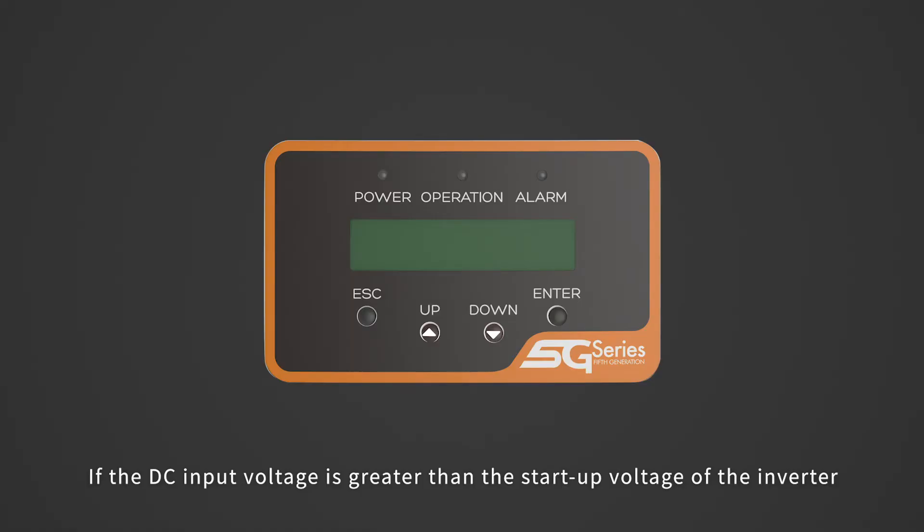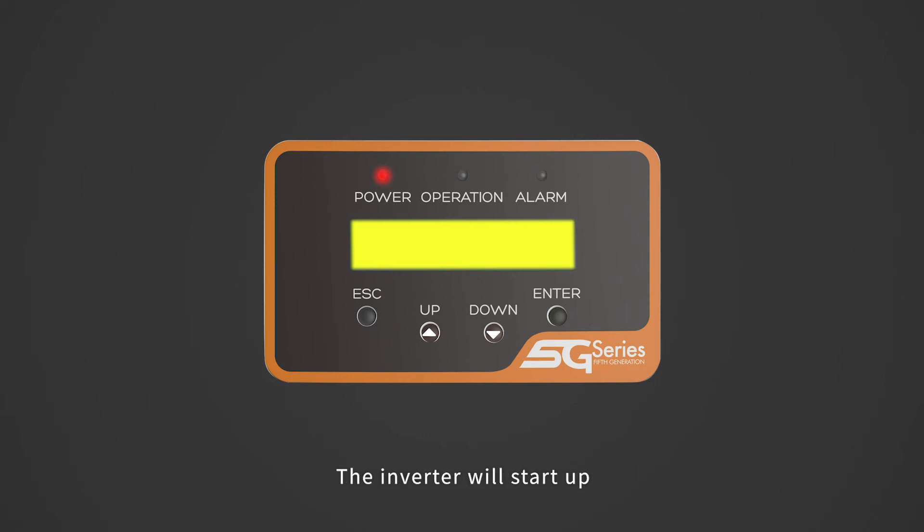If the DC input voltage is greater than the startup voltage of the inverter, the inverter will start up. After the self check is complete, the screen will show waiting. After the local mandatory delay ends, the inverter will start normal operation.